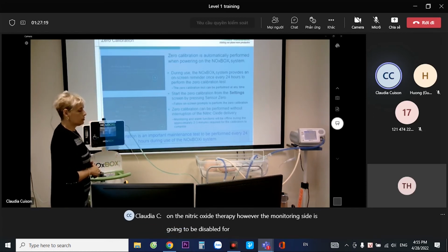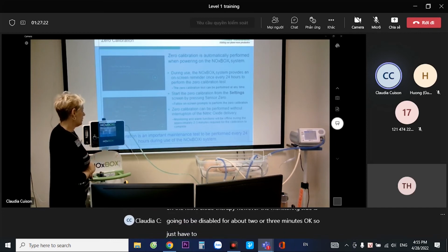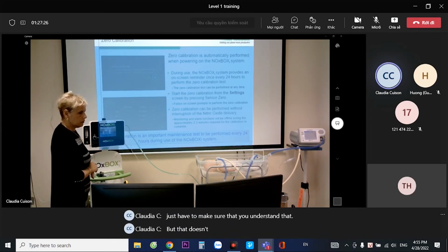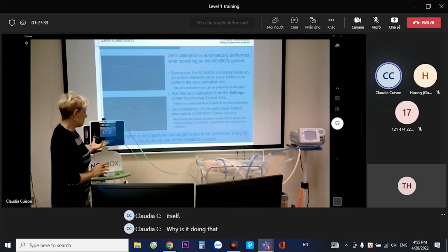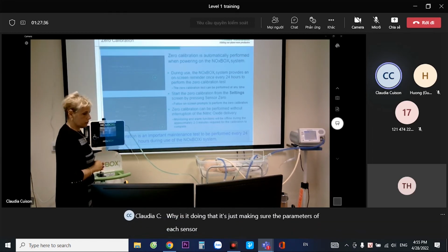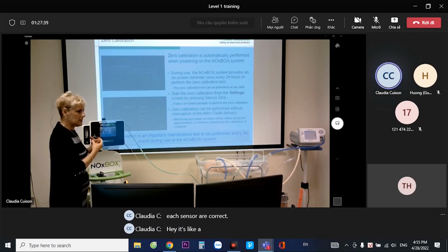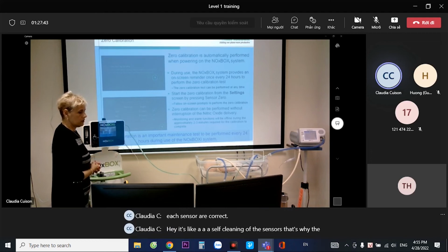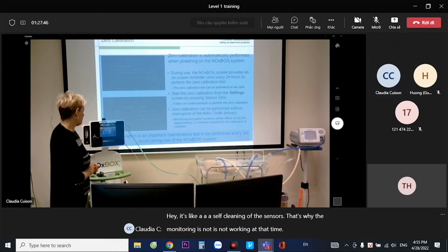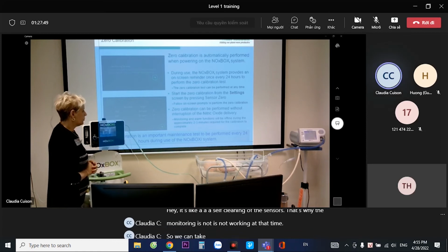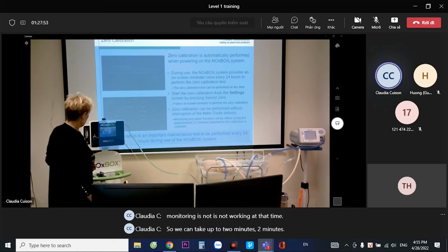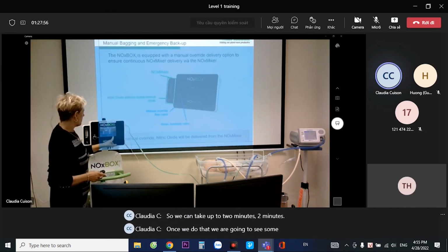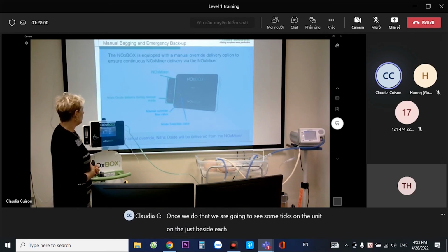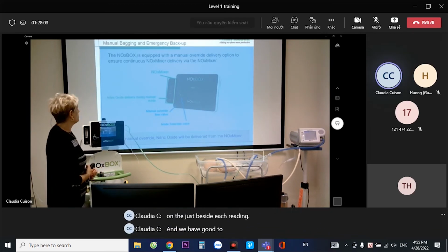However, the monitoring side is going to be disabled for about 2 or 3 minutes. Okay, so just make sure that you understand that. But that doesn't really make any big impact on the therapy itself. Why is it doing that? It's just making sure the parameters of each sensor are correct. It's like a self-cleaning of the sensors. That's why the monitoring is not working at that time. So it can take up to 2 minutes. Once we do that, we are going to see some ticks on the unit, just beside each reading, and we are good to go, or ready to go.